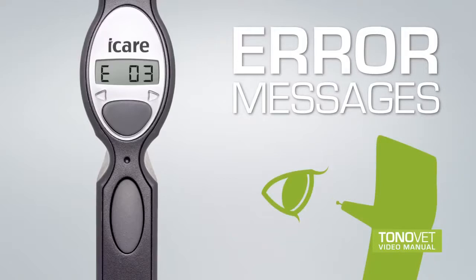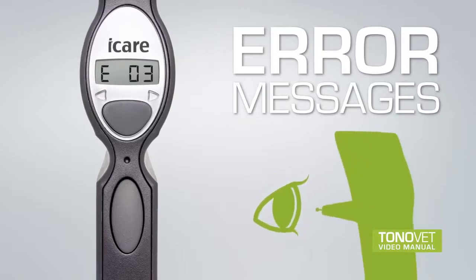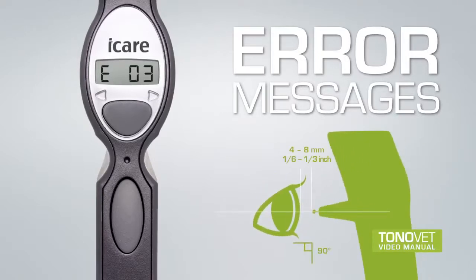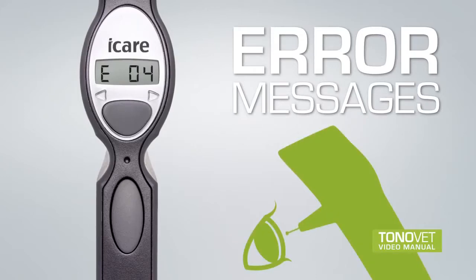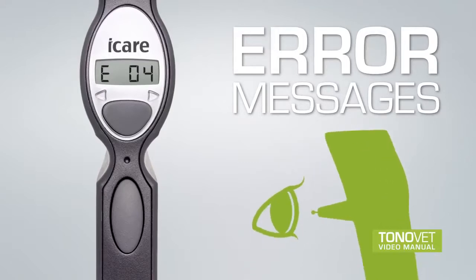E03 indicates the probe speed was too low because the measurement was made from too far away, or the tonometer was tilted upwards too much. Adjust position of the tonometer. Make sure the probe is in a 90-degree angle towards the eye with a distance of 4 to 8 millimeters, and repeat the measurement. E04 indicates the probe speed was too high because the tonometer was tilted downwards. Adjust the position of the tonometer and repeat the measurement.